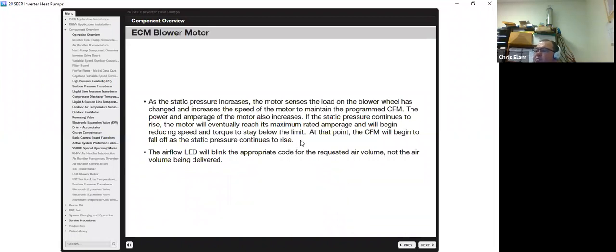to your static pressure. So if you're going to sell, especially if you're going to sell a full communicating inverter system, do a static pressure test on the existing ductwork before you sell it. Otherwise, if you realize after the fact that your static pressure is excessively high, it's hard to sell ductwork after the fact. So preempt that by checking out the system of ductwork ahead of time and then adjusting and modifying the ductwork as necessary.